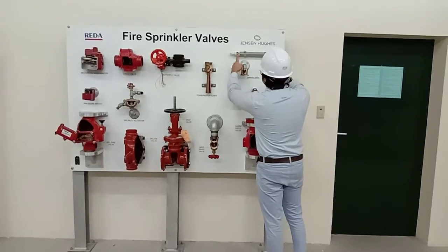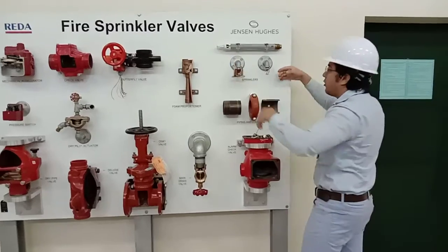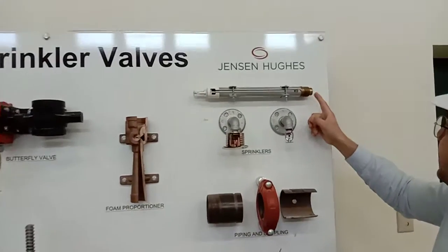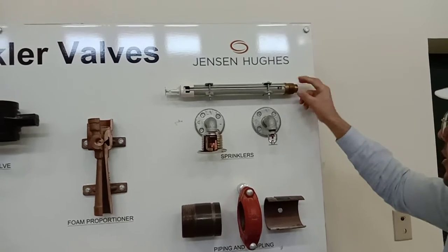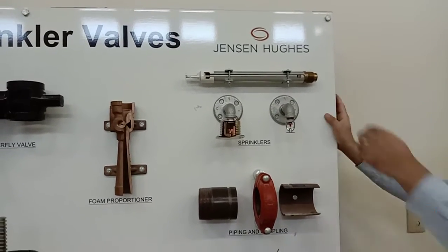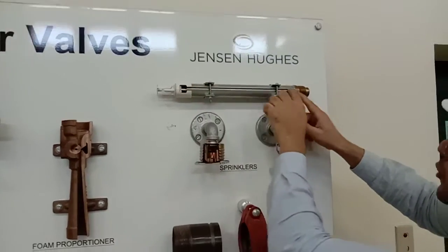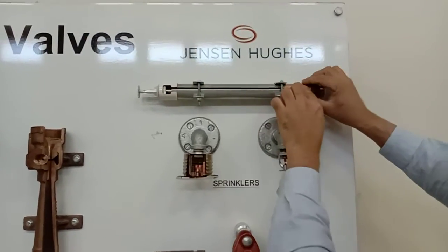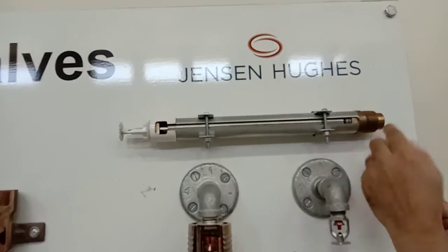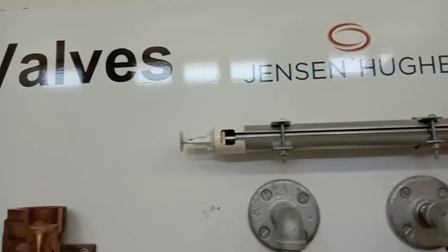The function of the dry sprinkler is that it is just like a pendant head — a pendent head hanging toward the bottom of the surface. The connection at the top is taken from the main pipes. This is a dry barrel and there is no water inside it. The barrel sits inside the freezing atmosphere while the water supply side remains above.